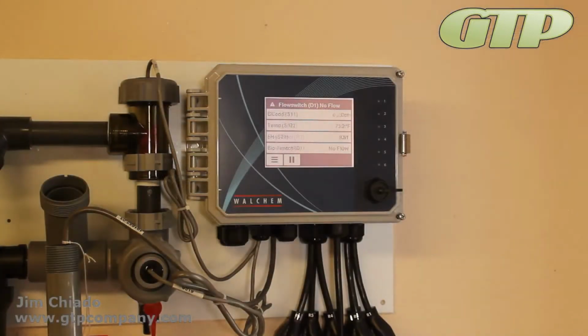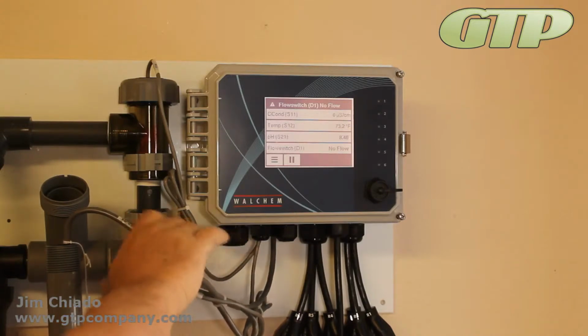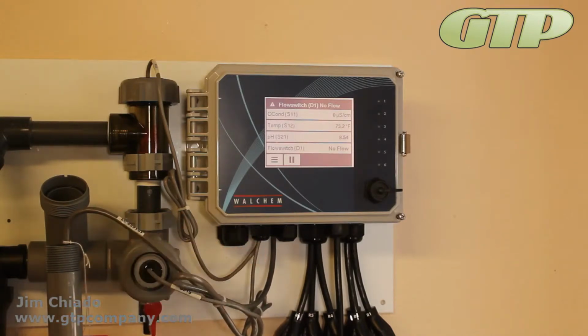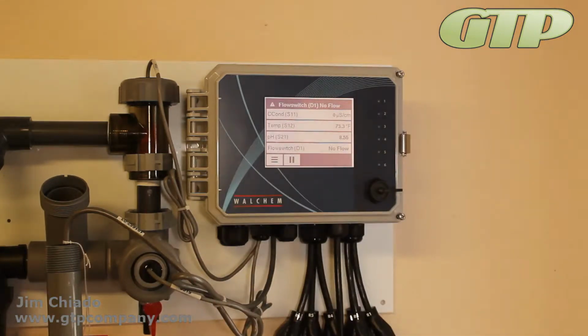Geometry Products video training. I'm going to do calibration on the pH now on a W600. So we did the calibration on conductivity, and conductivity 1 point, I don't mind it so much. You're really kind of just telling it where a 0 is unless you do the open air 0, which we did show you on that one. But it is linear, so 0 and 400 does have a slope to it.